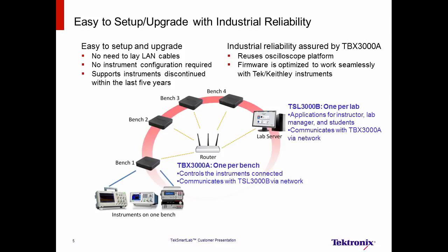We said TekSmartLab is easy to set up, and it is. It can be set up via Wi-Fi without laying LAN cables, and instruments are automatically recognized without any configuration when connected to the TBX3000A. It is also easy to upgrade the existing lab, as most Tektronix and Keithley instruments, even discontinued ones, are supported.